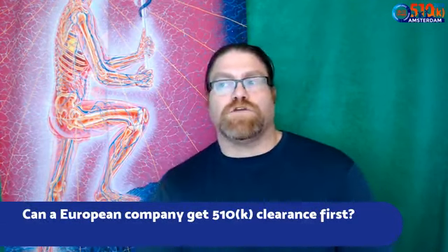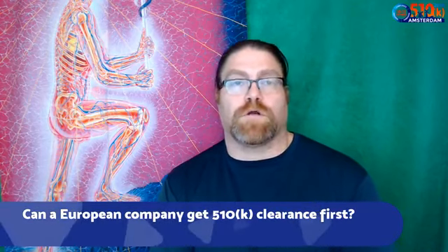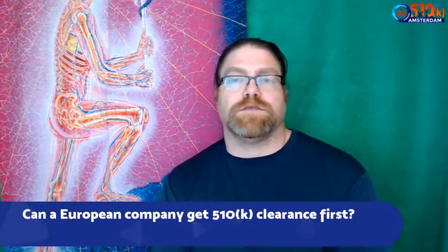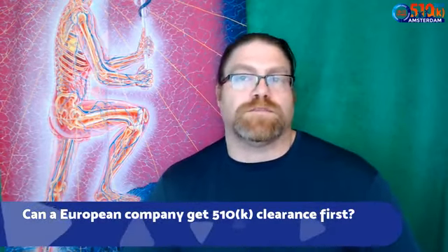Another question: can a European company get 510K clearance first? Of course. You're not required to have CE marking or approval in your country, regardless of what country it is, in order to submit in the US. It's helpful to know, but not required. So you can submit just to the US and they'll decide whether it's approved in the US, regardless of what the status is in other countries.